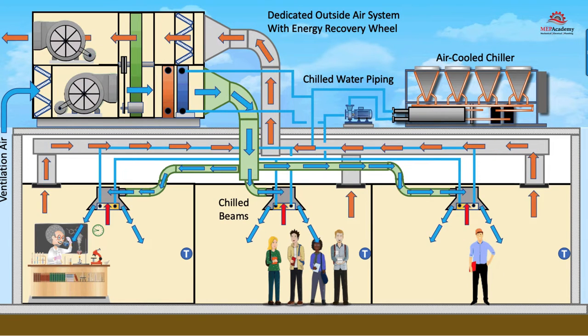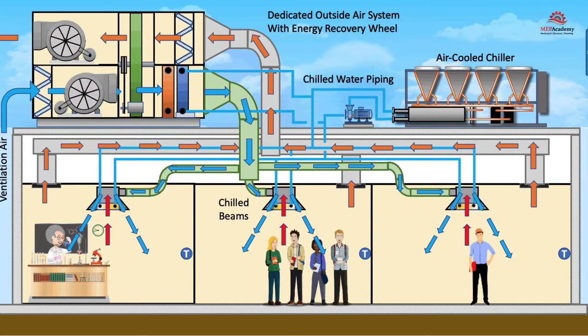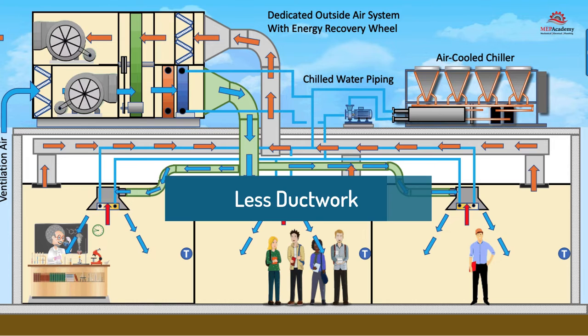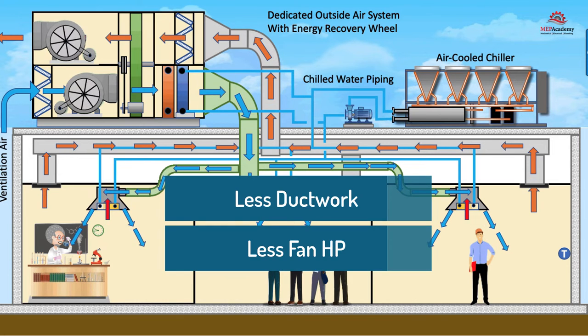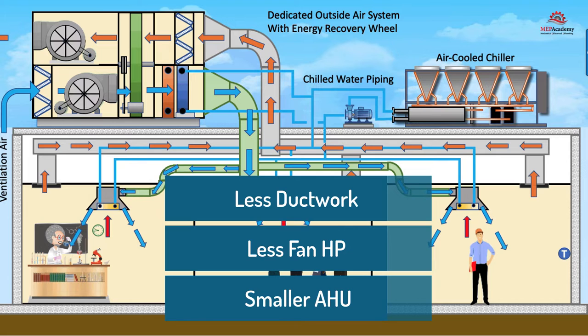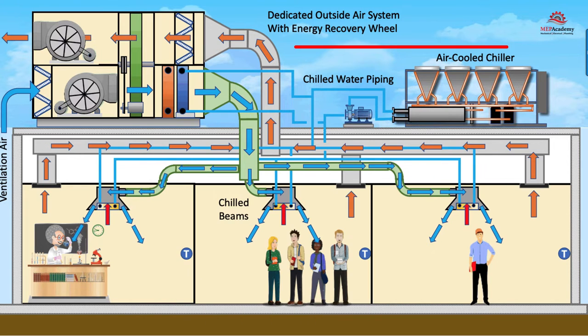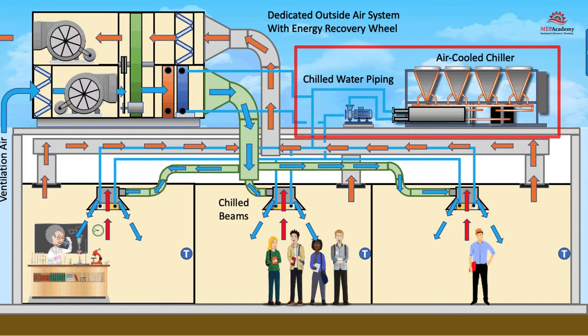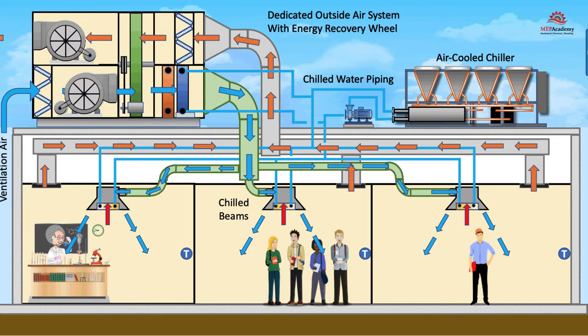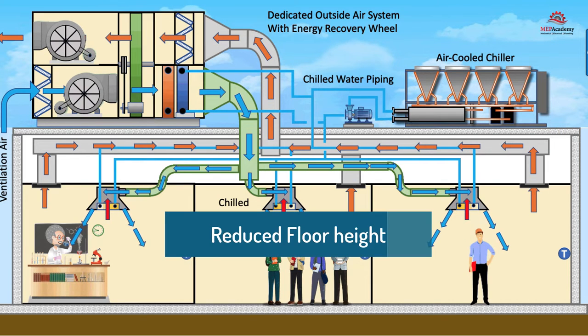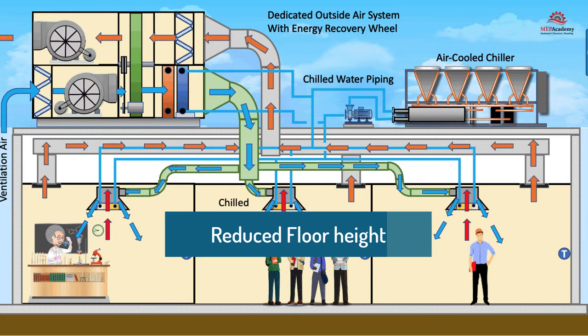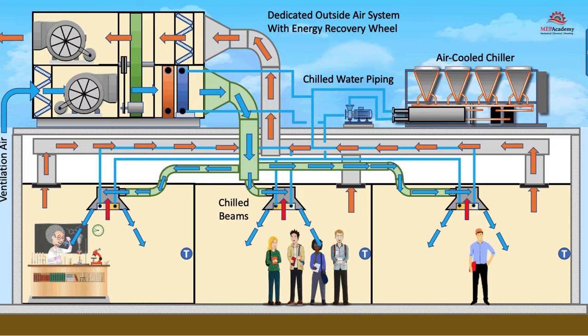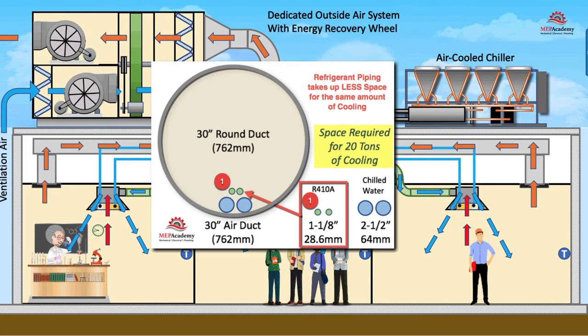Since the cooling is being done at the space level and not back at the air handling unit, less ductwork and fan horsepower are required, including a smaller air handler. Chilled water and ventilation air will need to be brought to the space. This could also allow for a reduction in floor-to-floor height, as less space is taken up in the attic for larger air ducts. More energy can be carried in a small pipe than a large duct.